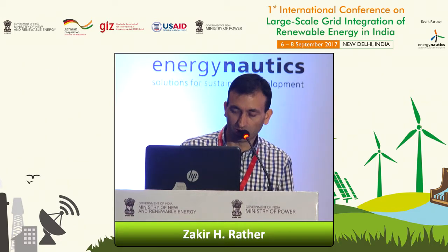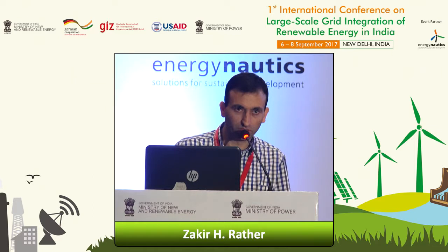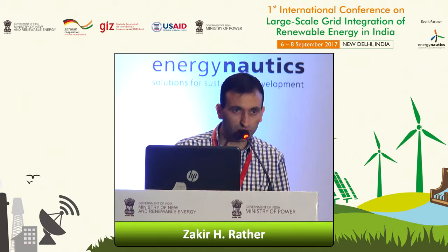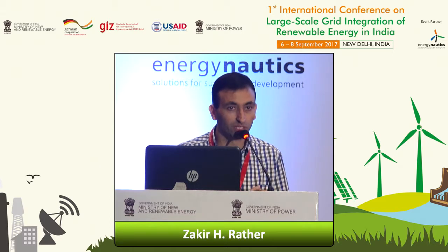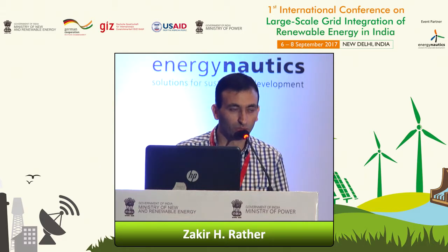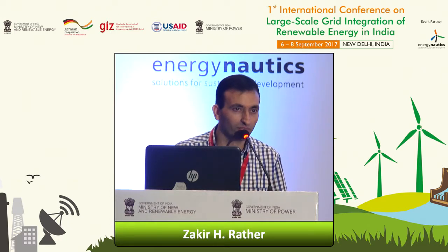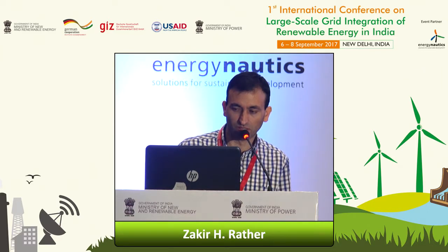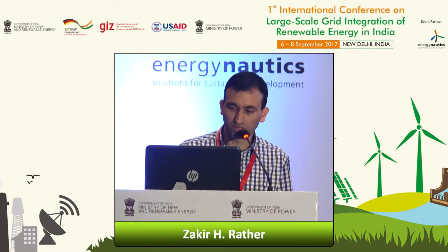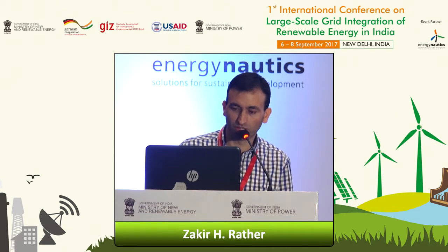We try to have two control loops in the wind power plant or wind turbine, where we can have both droop response as well as inertial response. Droop response is primarily meant here for fast frequency. Wherever we have headroom in the wind turbine, we can use that to support the grid. For example, in some cases, if we have curtailed wind, we can use that to support the frequency of the grid. This is a bit more of the internal details of the model, and I think it's not very relevant to discuss in detail.